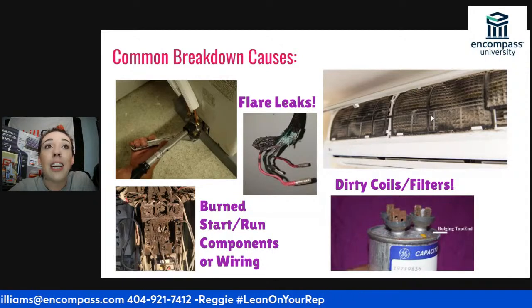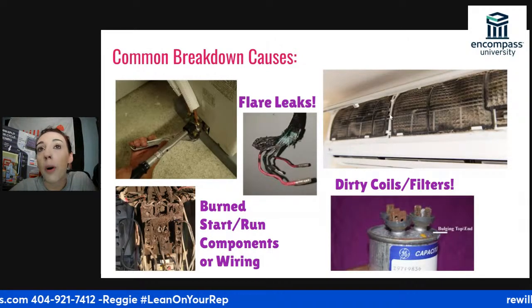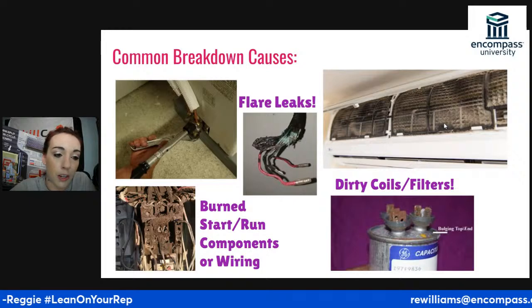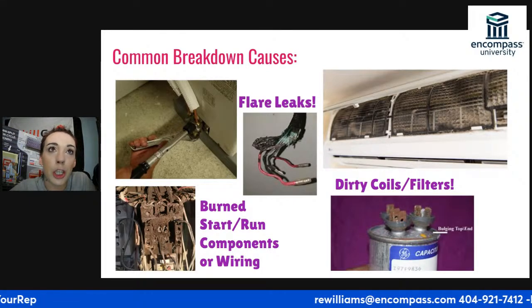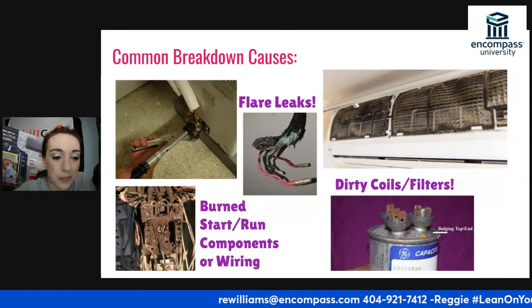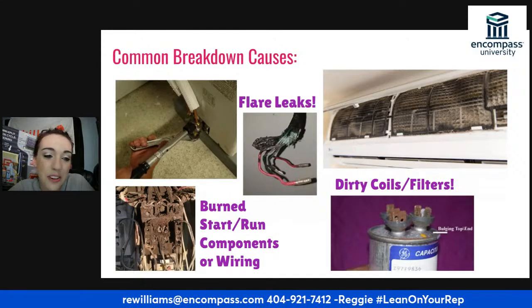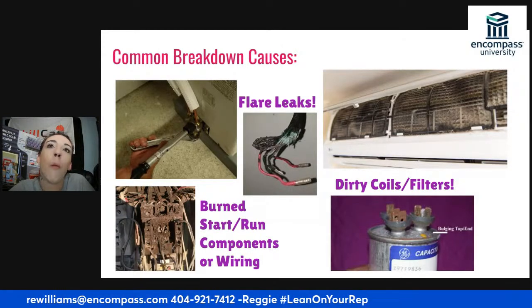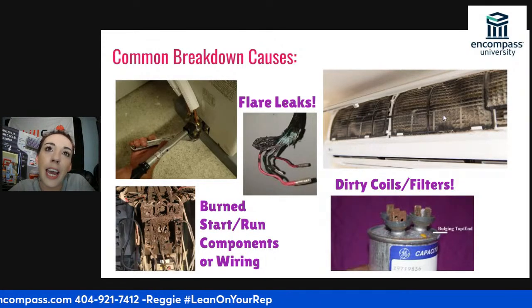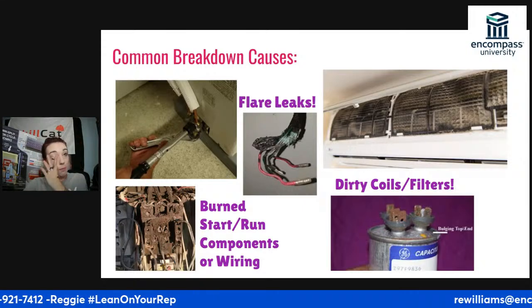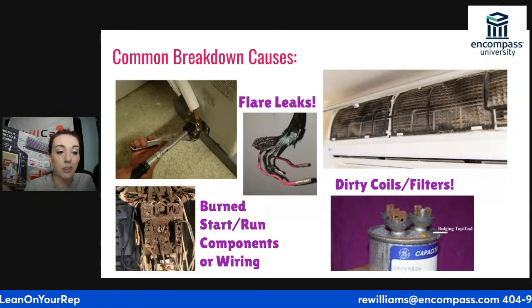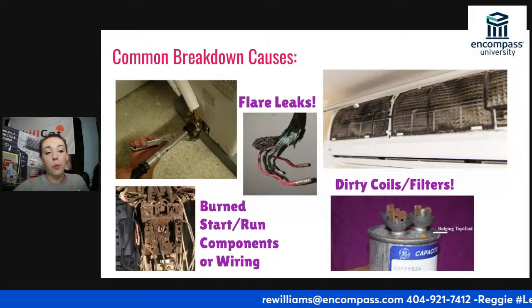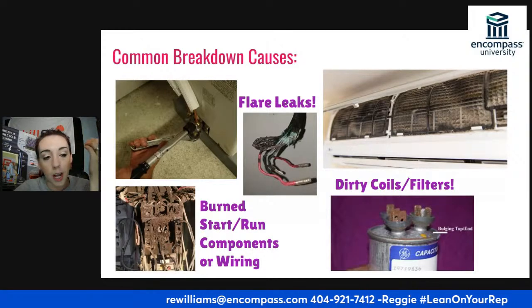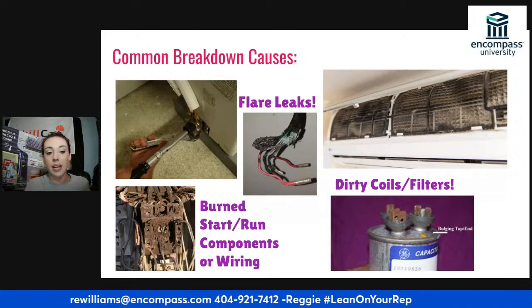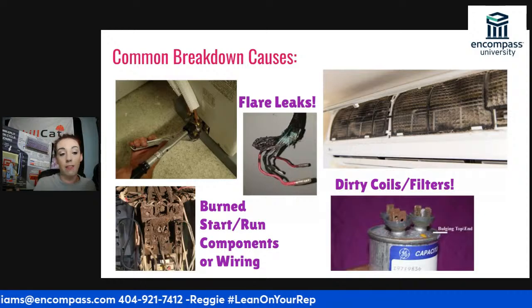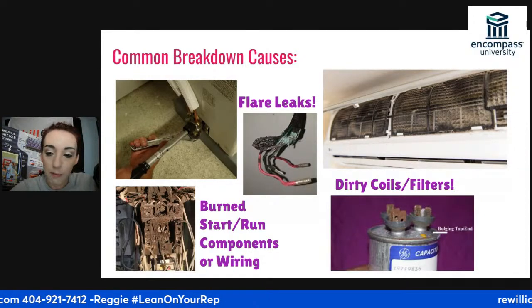And then behind that is your coil. If this filter looks like this, your coil looks even worse, I promise. And we need to make sure that we're doing the dollar bill test, we like to call it. I call it that for my new technicians. The dollar bill test means that while the unit is running, you'll have to do it on the outdoor unit or the indoor unit, depending where your reversing valve is, whether you're in heat or cooling. But you want that coil to be able to hold a dollar bill against the coil without any help. If you can't, then you have a lack of airflow and you need to do a better job cleaning.